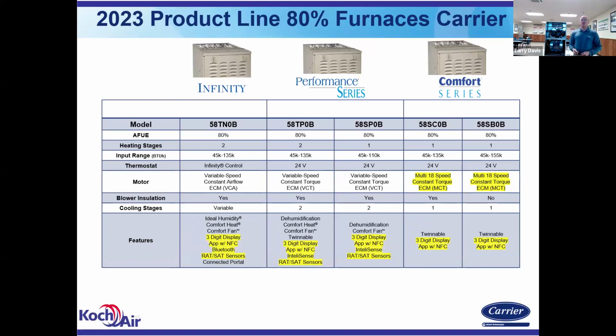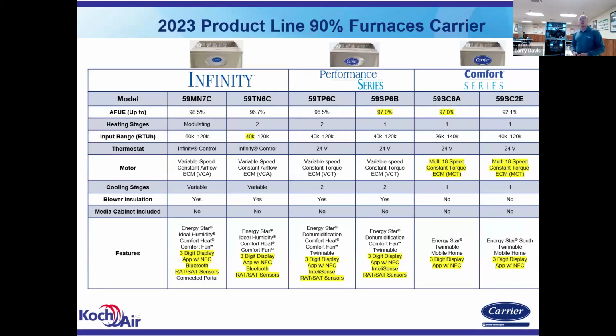And you can see that the new Comfort series for Carrier has an 18-speed constant torque ECM motor in it, and they all have the 3-segment LCD display with the near field communication antenna built in. On the mid-tier and the Infinity, they also have a terminal on here for supply air and return air temperature sensors. That is for the IntelliSense service that's available. And the communicating systems come not only with near field communication, but with a Bluetooth module.